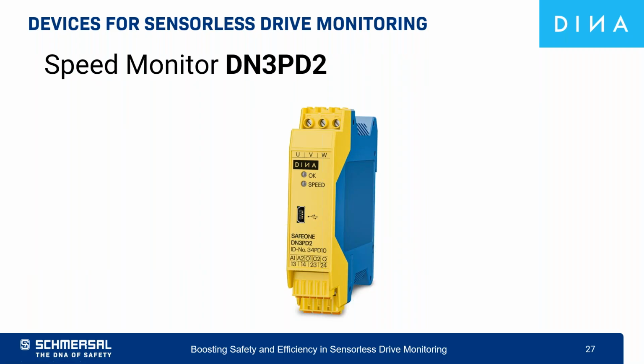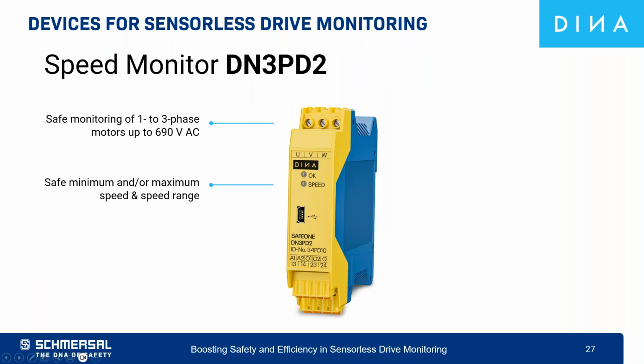We were talking about motor compatibility. So as Steve and Samuel mentioned, you can use it for 1- and 3-phase motors up to 690 volt AC. Also for motors in star delta circuit. And you can monitor safe minimum, maximum speed, or minimum or maximum speed, and also a speed range.